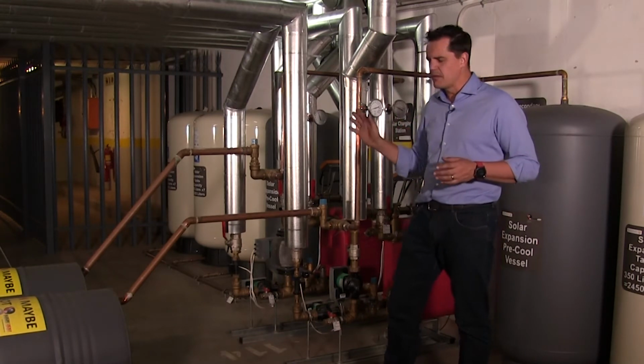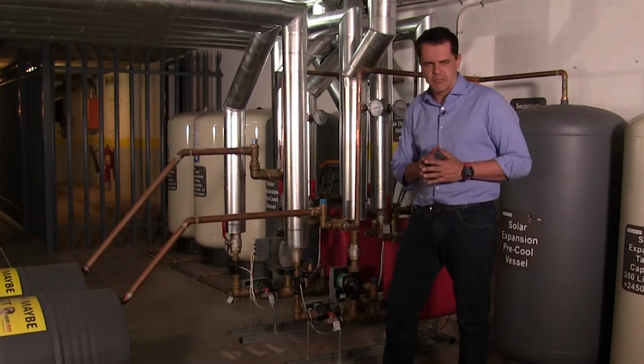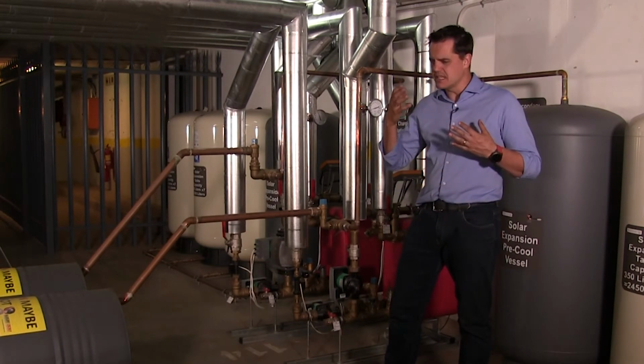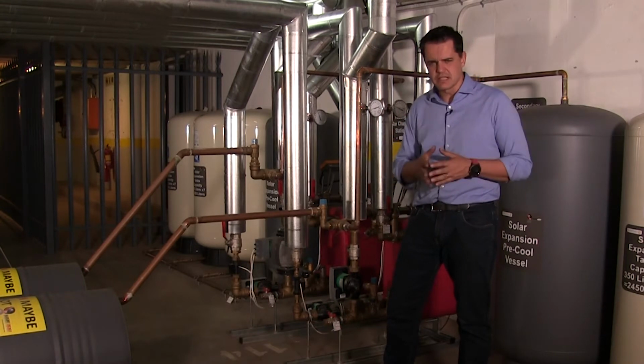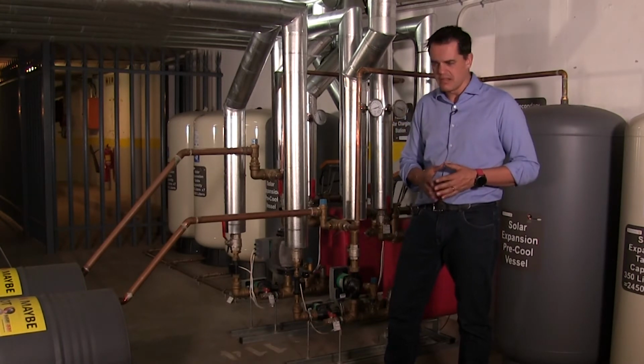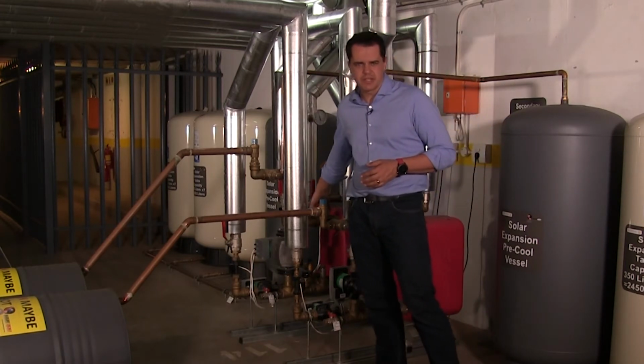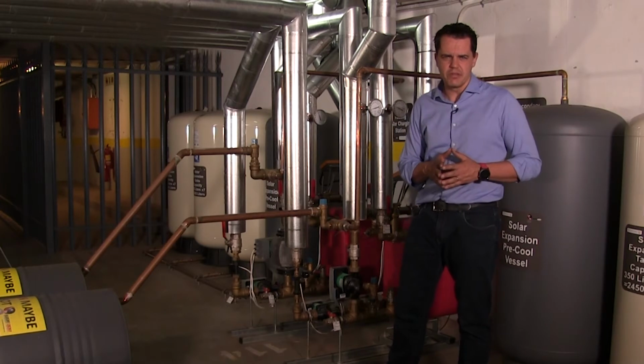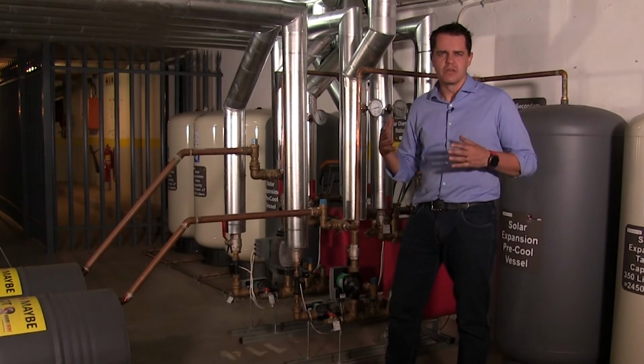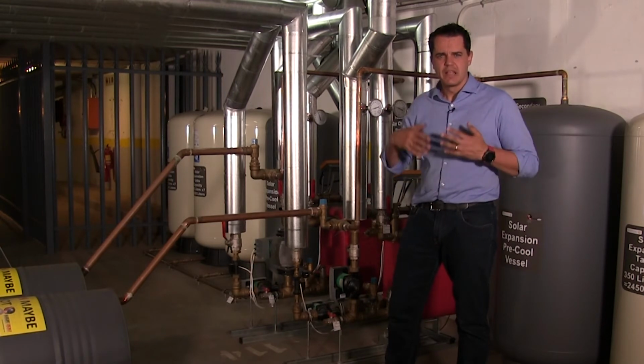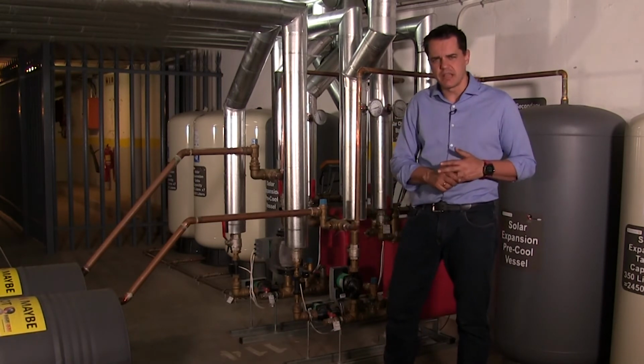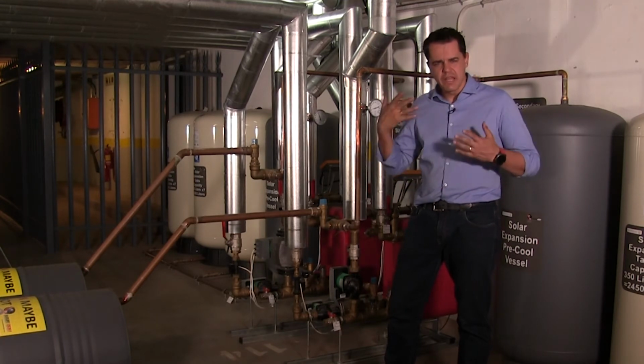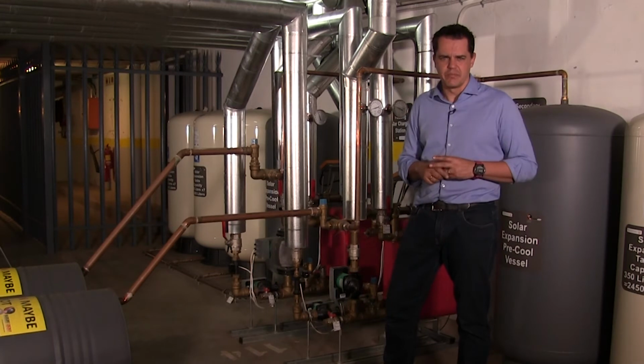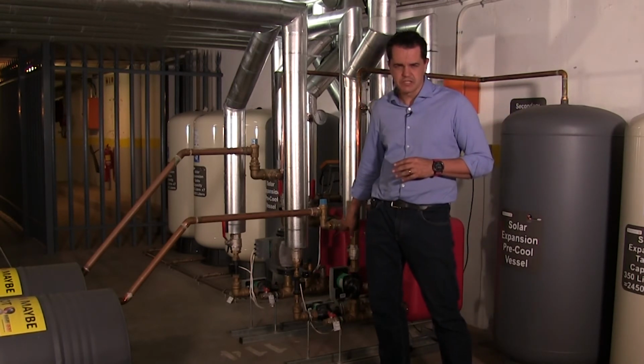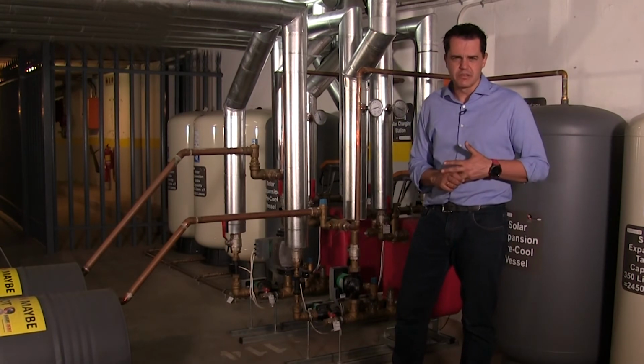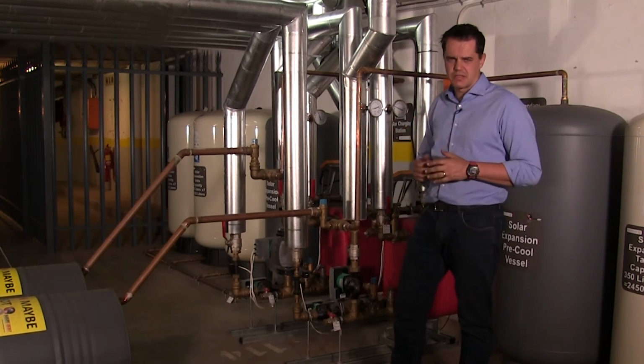If at any point, and maybe not even if it's released glycol into the drums, maybe there is a fitting on the top of the roof that has gone loose and it's leaked out glycol, you'll be able to identify it by looking at the pressure gauge. So if the pressure gauge does not show 3-bar, maybe it shows 1 bar, we know that somewhere a pipe joint has failed, the glycol has leaked out, and the system doesn't have the necessary pressure to circulate. Again, you then notify the contractor, but you can identify the problem by saying there's no pressure in the solar loop, or it has released glycol into the drums. Please come inspect, but the solar system is not functional.